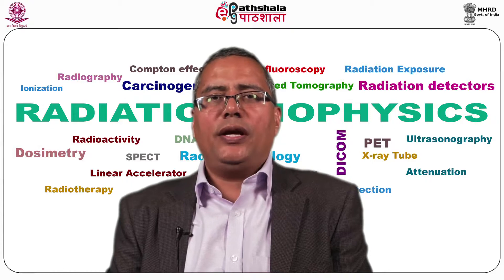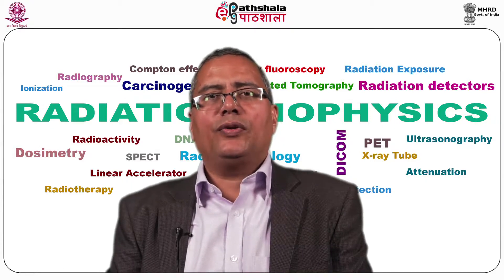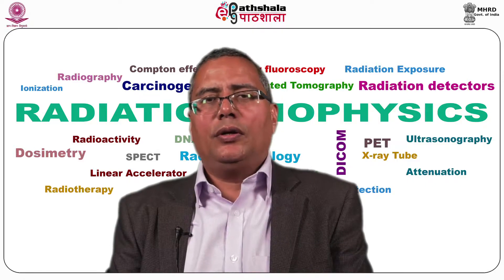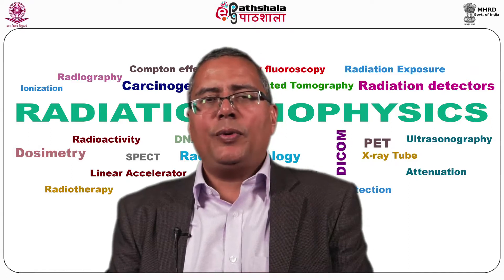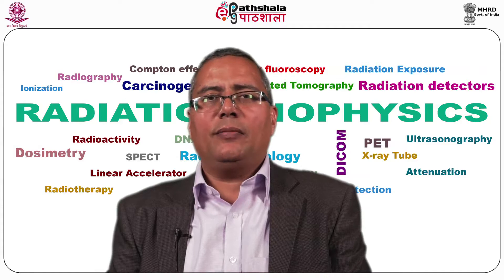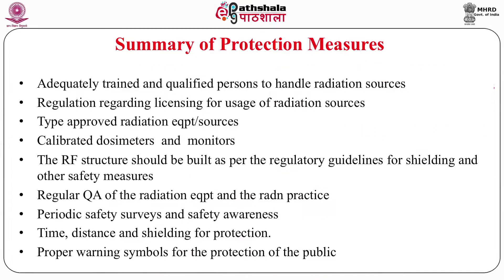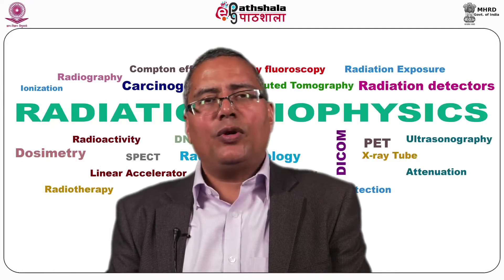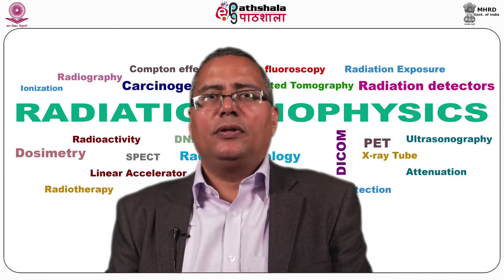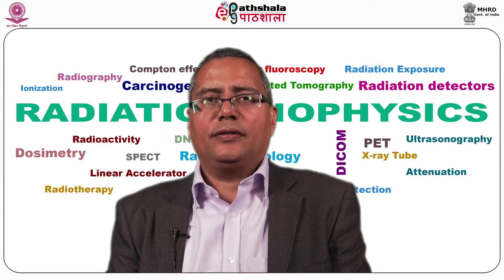To summarize radiation protection measures: trained radiation professionals authorized by AERB must be employed; radiation facilities must comply with AERB safety codes regarding shielding, monitoring equipment, and safety measures; regular quality assurance and calibration of radiation-generating and radiation-measuring equipment must be carried out at periodic intervals; radiation warning symbols must be placed at conspicuous locations; and all radiation workers must follow safety guidelines.